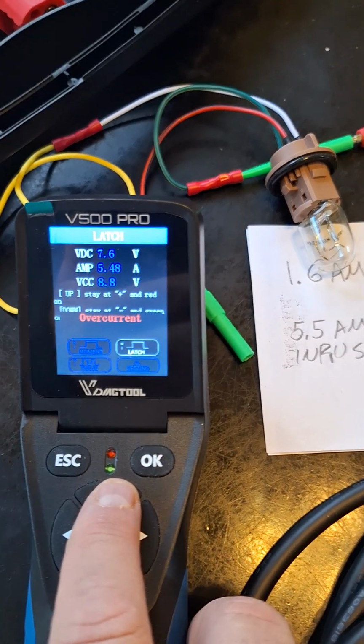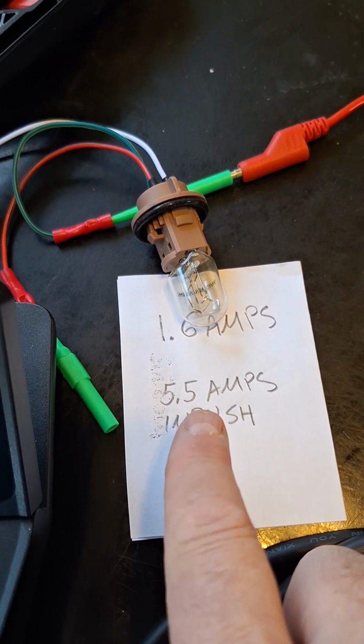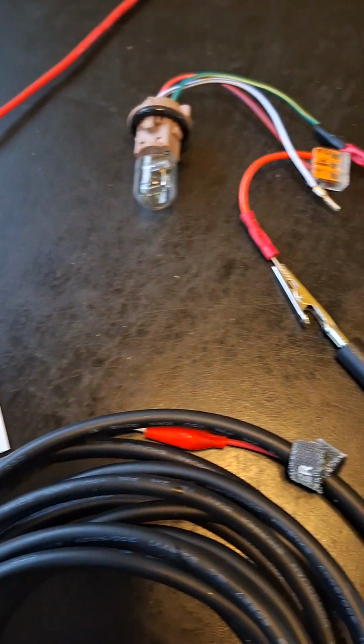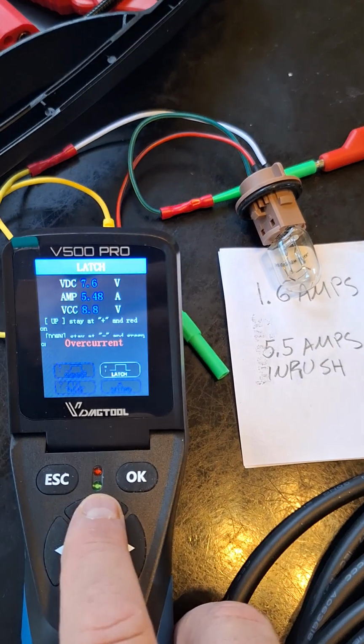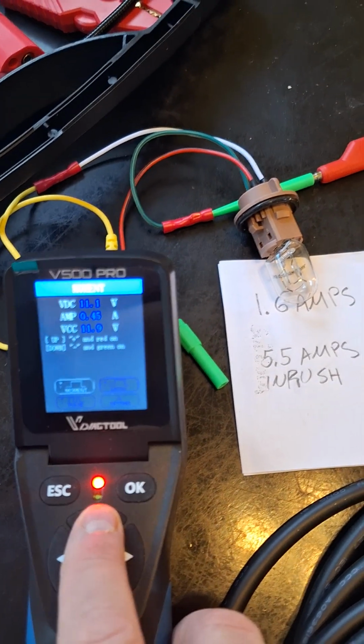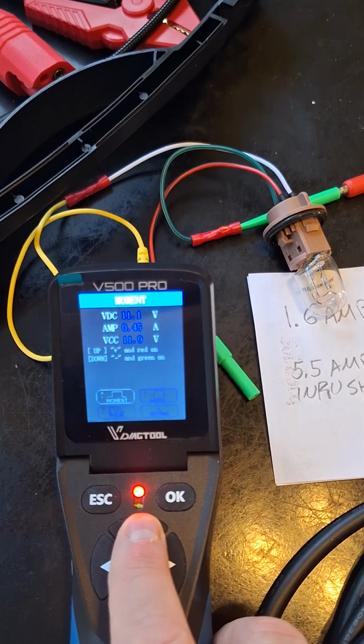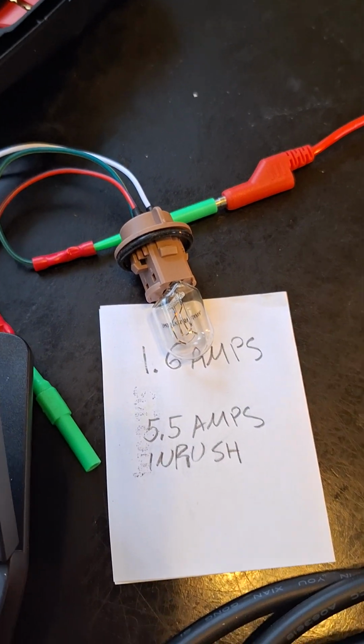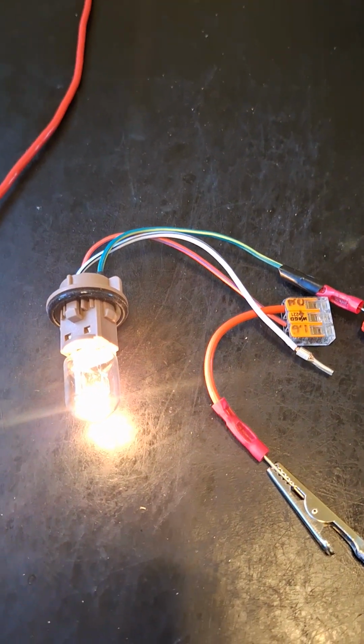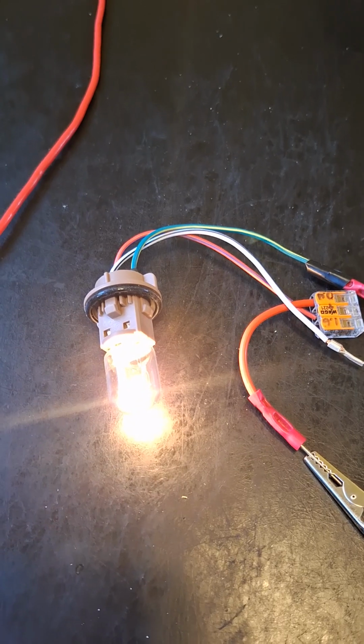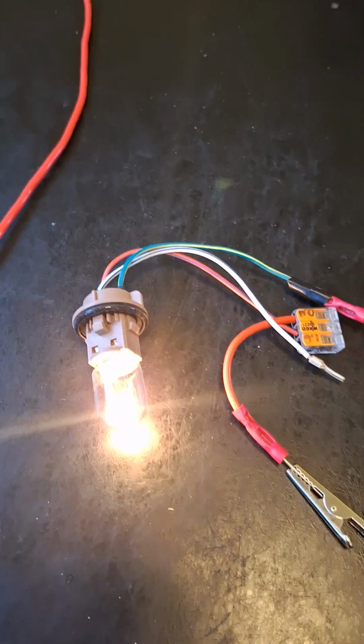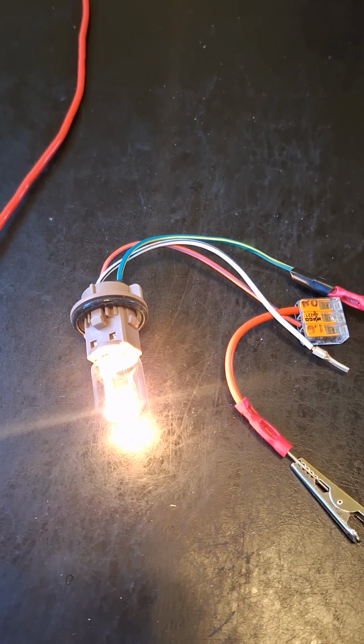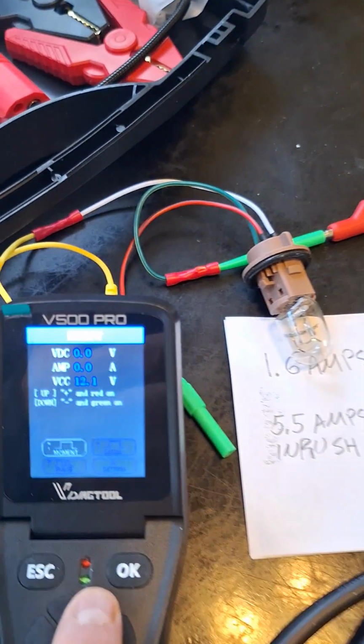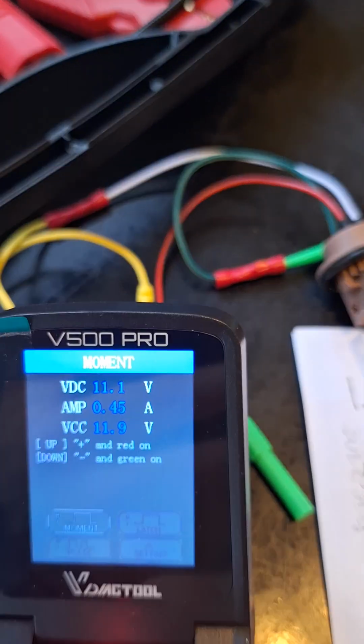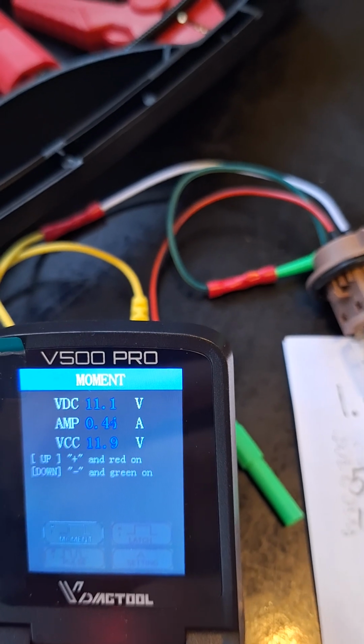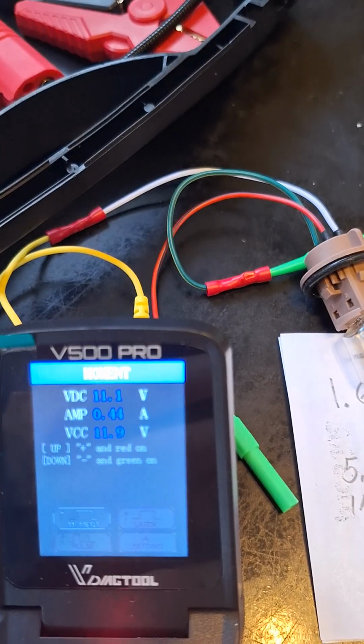Again, we're set at 5 amps here, which normally would trip the circuit, but because of this resistor, let's see what happens. It doesn't trip the breaker, doesn't light this bulb. It does light this bulb. This basically represents your corrosion or your bad connection that's using up voltage. Also, you'll see that this is limiting the current here to 0.45 amps.